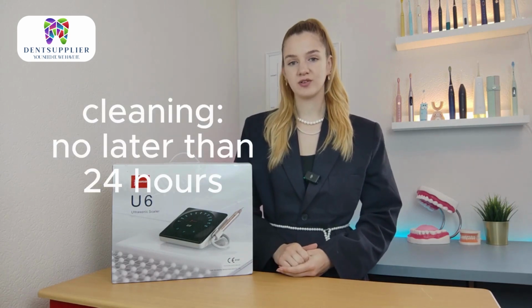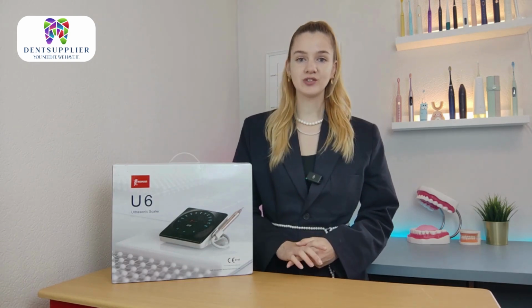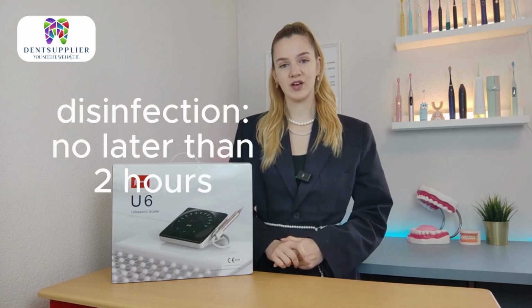And now let's talk about maintenance and care of the U6. The cleaning should be performed no later than 24 hours after the operation, and disinfection must be performed no later than 2 hours after the cleaning phase. The products have been designed for a large number of sterilization cycles. The materials used in manufacture were selected accordingly.